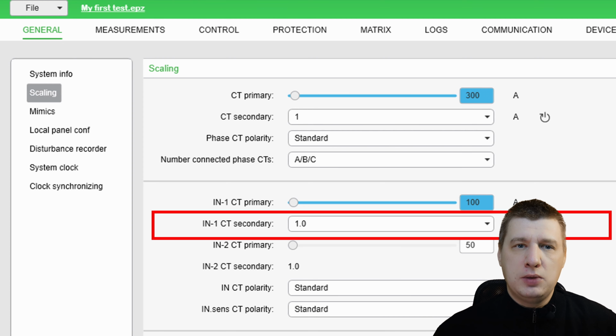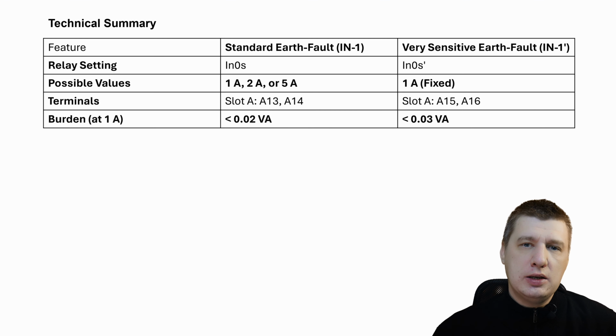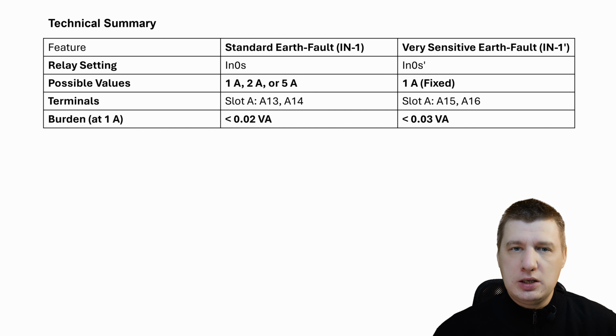When you set this up, make sure that it matches the label on your physical CTs. If your CT says 50:1, your primary is 50 and the secondary is 1. Match those in the scaling view. Choosing the right rating is the difference between catching the fault early and missing it entirely. Check your CT nameplates, set it correctly, and stay safe. Using 1 amp secondary for earth fault is like using a microscope instead of a magnifying glass. While a magnifying glass, 5 amps, is great for looking at a large object, a microscope, 1 amp, lets you see tiny details that are invisible to the naked eye, allowing you to catch sickness in the electrical network.